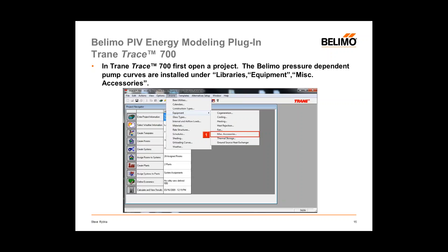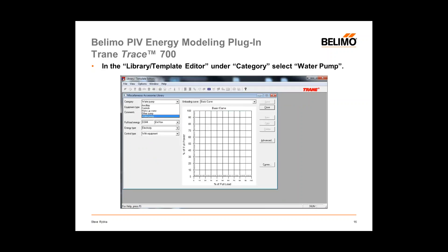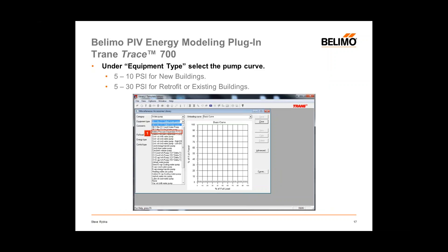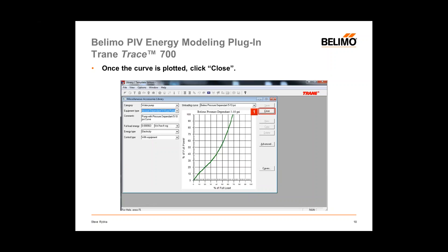Now let's look at Trane TRACE 700. After installing the plug-in and opening the project, the pressure-dependent curves are installed in the Miscellaneous Accessories tab under the Library section in Equipments. Once you get to the Library Template Editor, under Miscellaneous Accessories Library, select Water Pump. After the Equipment Type is selected, choose the applicable pump curve — 5 to 10 PSI for a new building, or 5 to 30 PSI for retrofits. Once the curve is plotted, click Close.